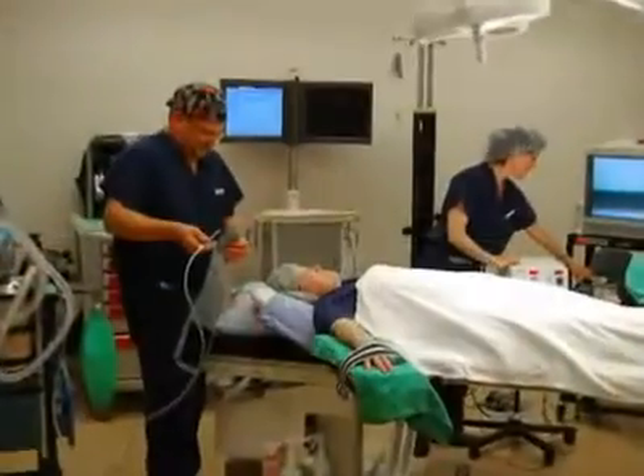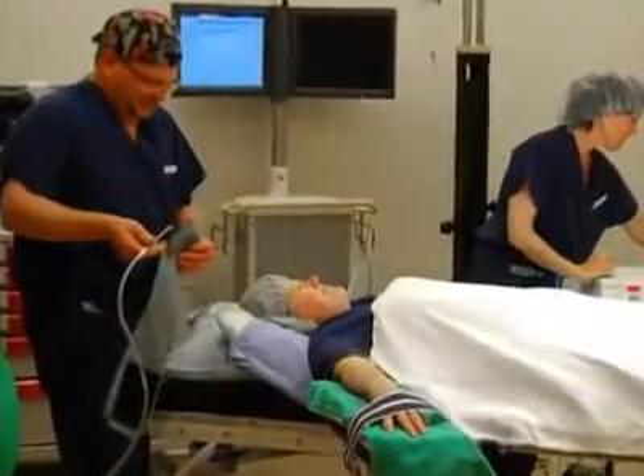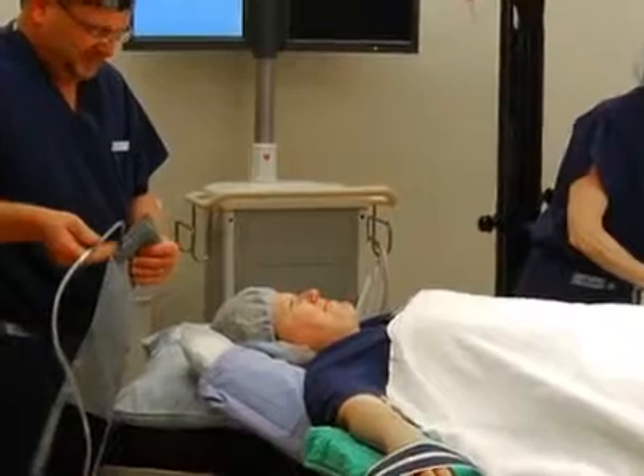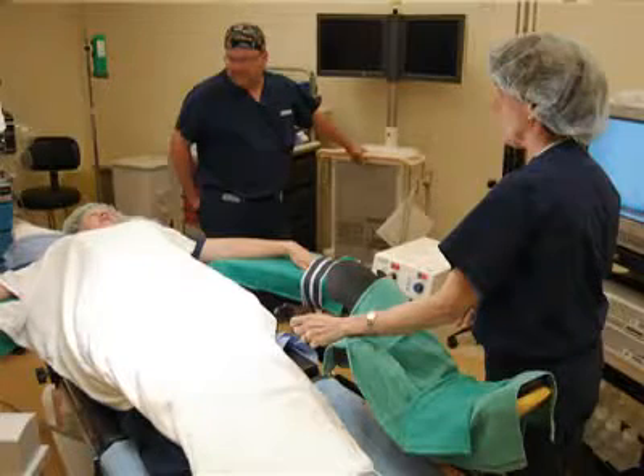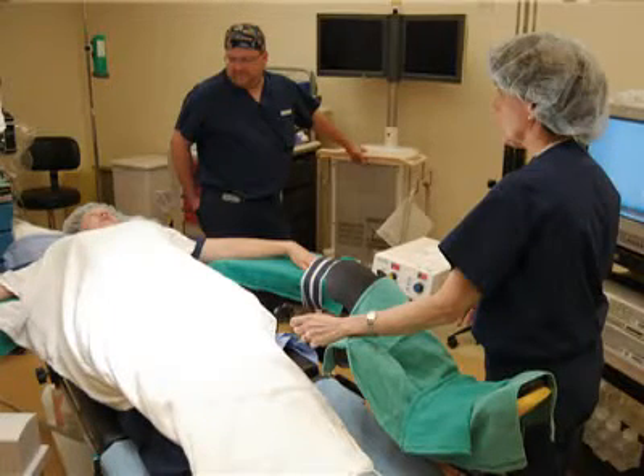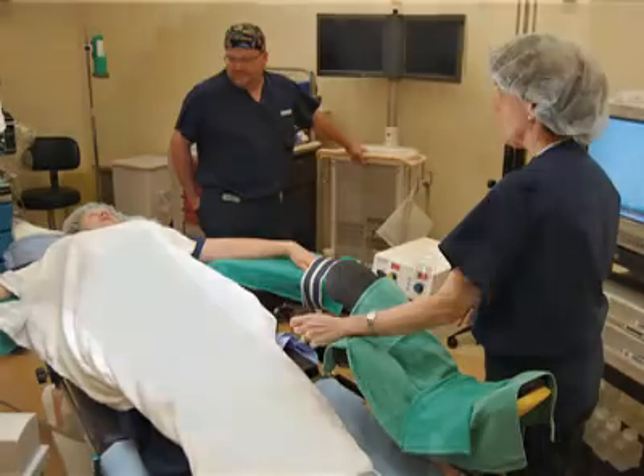By utilizing an ungrounded or isolated power system in an operating room or any other critical care procedure room, we're better able to monitor and manage potentially hazardous electrical leakage currents that could circulate through the medical devices in use as well as the permanent circuitry inside the room.